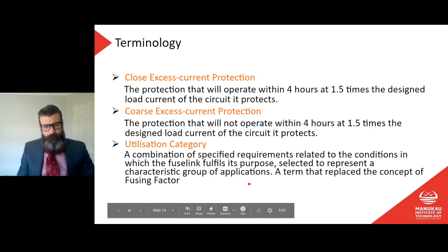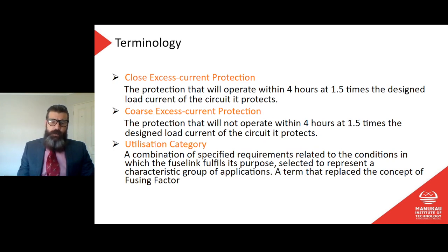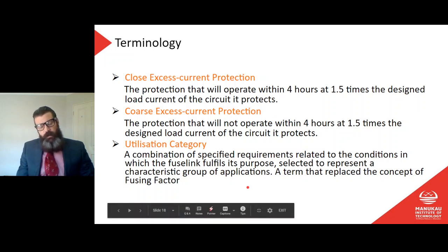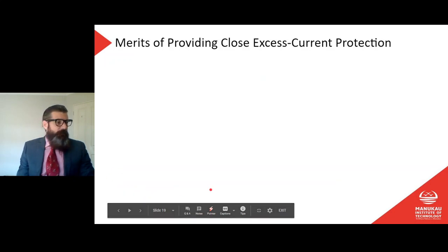Let me read that again. A combination of specified requirements related to the conditions in which the fuse link fulfills its purpose, selected to represent a characteristic group of applications, a term that replaces the fusing factor. Look, that doesn't tell us what that means. It just says there are some conditions that you need to know, and we talk about utilization category instead of fusing factor. Now, we've already gone through fusing factor, and the fusing factor is the one that you need to know for the test. So let's not worry too much about utilization characteristics.